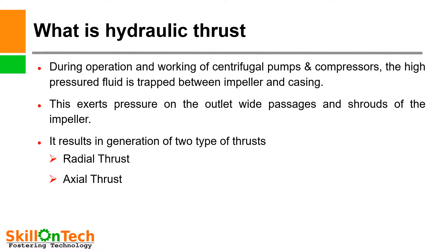What is hydraulic thrust? During operation and working of centrifugal pumps and compressors, the high pressure fluid trapped between the impeller and casing exerts pressure on the outlet wide passage and shrouds of the impeller, resulting in generation of two thrusts. One is radial thrust and the other is axial thrust. Radial thrust is produced due to unbalance of hydraulic forces in the radial direction of the impeller, and axial thrust is produced in the impeller of pumps and compressors parallel to the rotor.